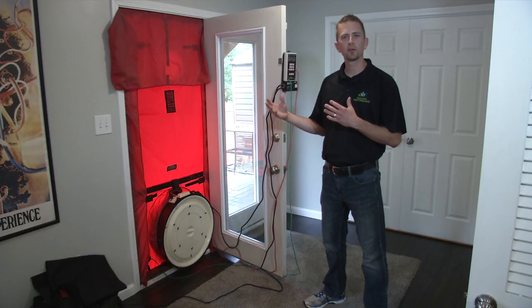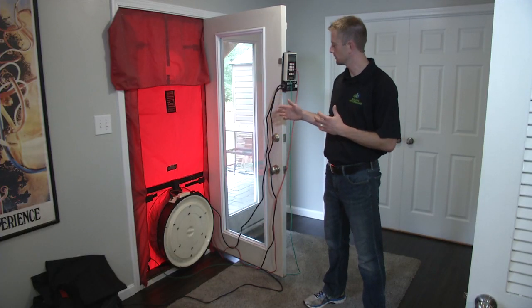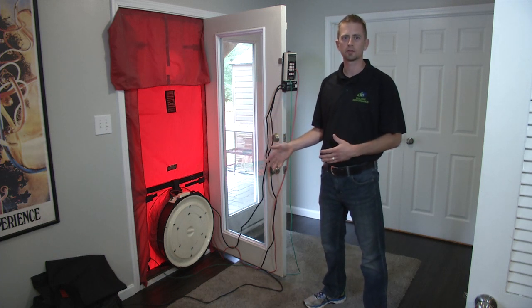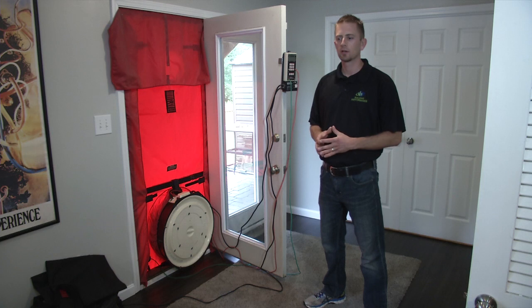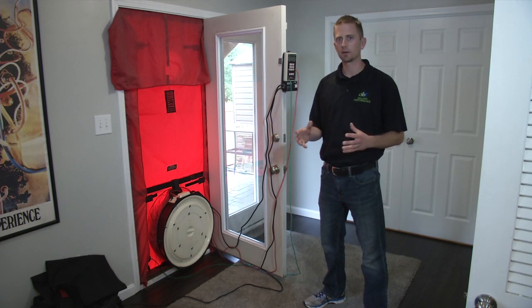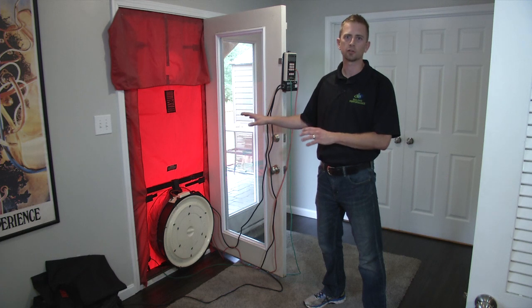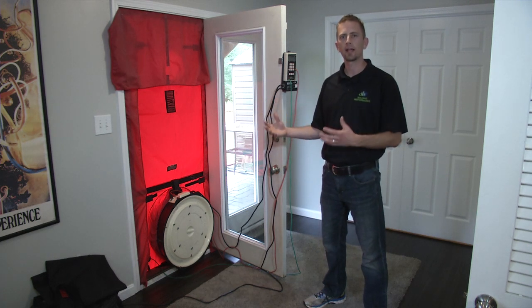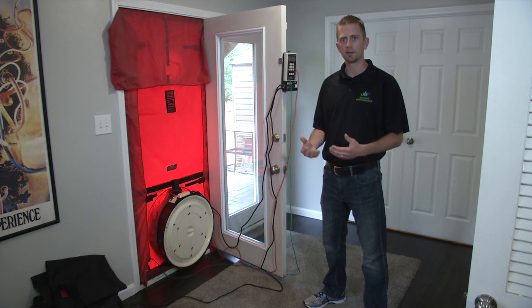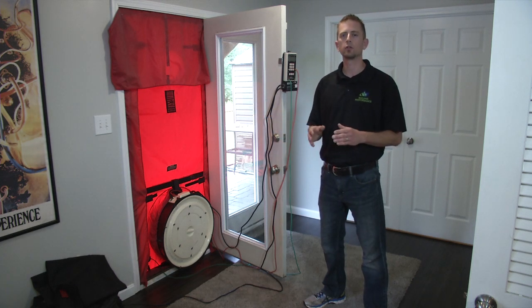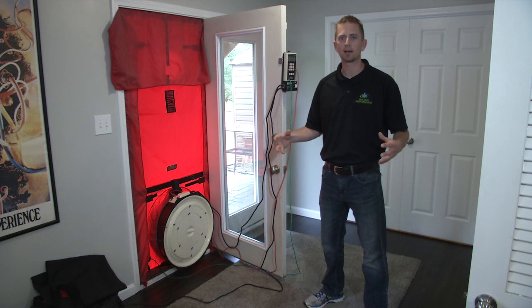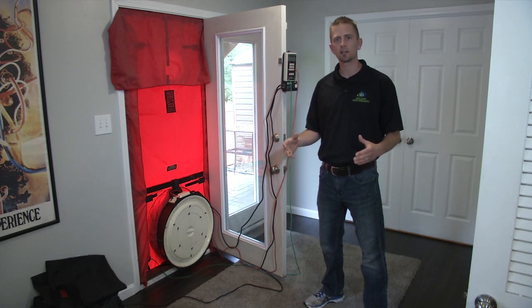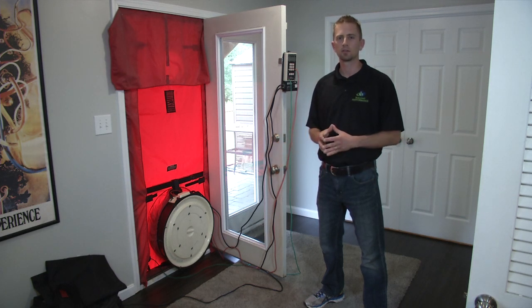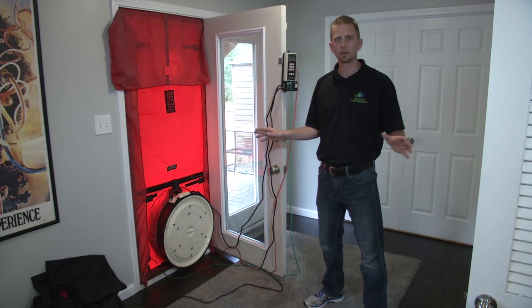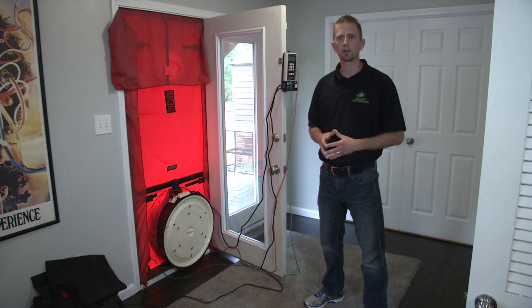Now we're in front of the blower door equipment, and this is what I use to simulate air leakage on the house when I do a duct blaster test. You need the blower door when you want to do a duct leakage to outside test, because this is what actually simulates air leakage on the house. Whatever air gets pulled into the house and into the duct system with the blower door, you then use the duct blaster to balance out that duct leakage, and however much air it takes for the duct blaster to balance out the leakage is the leakage to outside. So I'm going to show you how these two tests are run and how they're set up, and we're going to show you the results of the test.